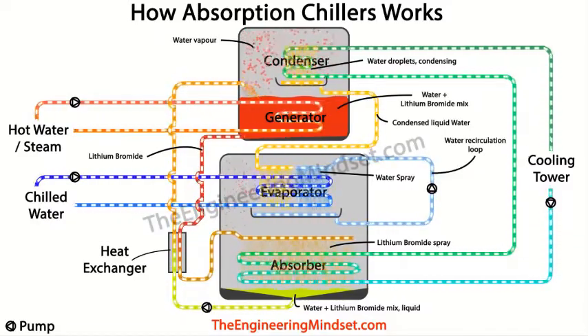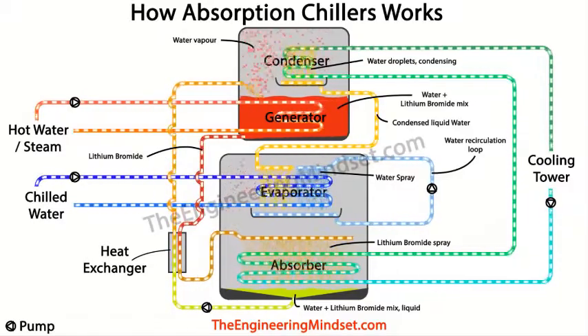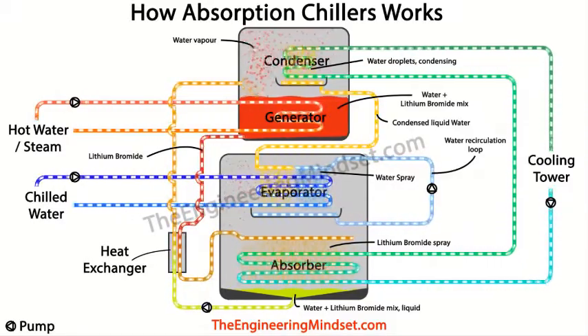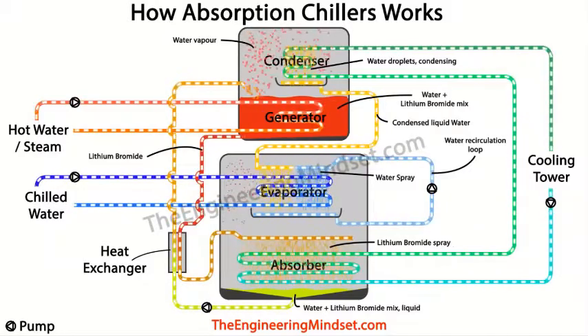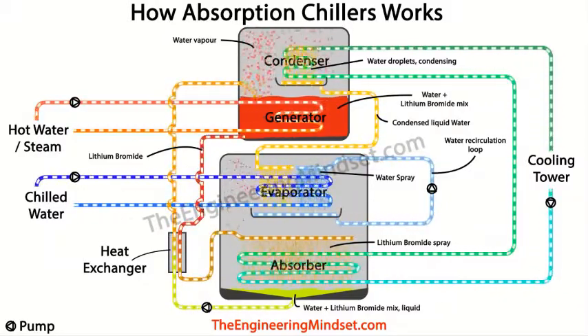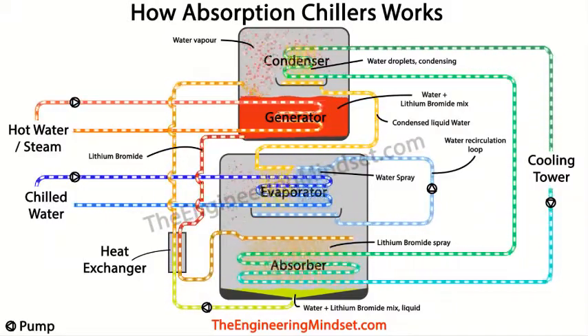Another loop will recirculate any water that missed the tubes and didn't boil off into steam or water vapor, and this will be pumped back to the top of the evaporator and sprayed again and again and again until all of it evaporates into steam.